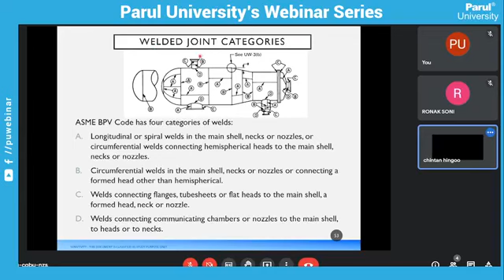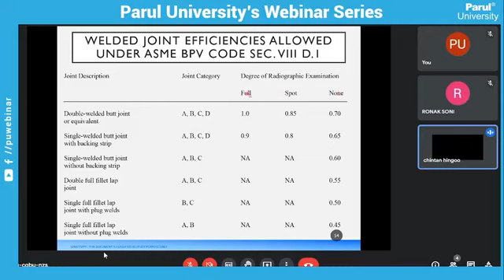Category C is like a flange to pipe joint, and category D is the corner joint of nozzle to shell junction. This is the figure from the ASME boiler and pressure vessel code. Based on the different categories, it is full, spot, and none. As I have shared, if you use full radiography, you will get joint efficiency factor 1. If you use spot radiography, you have to use 0.85. And if you are not doing any radiography or NDT examination, then your efficiency would be 0.7. So you can calculate that your thickness would always be higher. Again, this is the joint description, the joint category, and the extent of radiography examination.